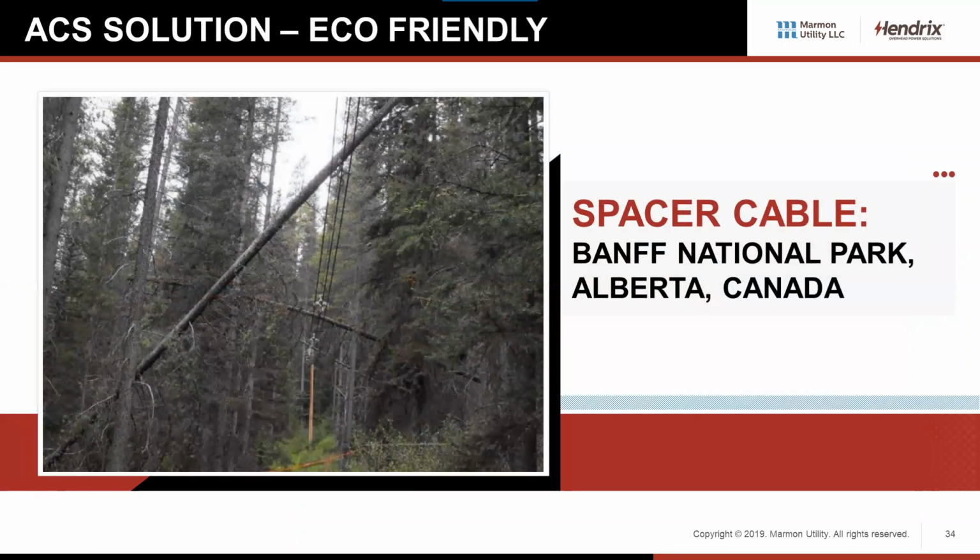Banff National Park, a lot of federal projects where they want to minimize tree clearing and tree trimming, look at using spacer cable. This one, a lot of the reason was these areas up here in this national park up in Canada are really, really difficult to access, a good 6 or 8 months out of the year because of the amount of snow that they get. So every spring and fall, they patrol all their spacer cable. And this was one of the first years that they did it. You can see there's 3 trees laying on this particular span, still up in the air, still energized. They just had to go ahead and remove those trees.